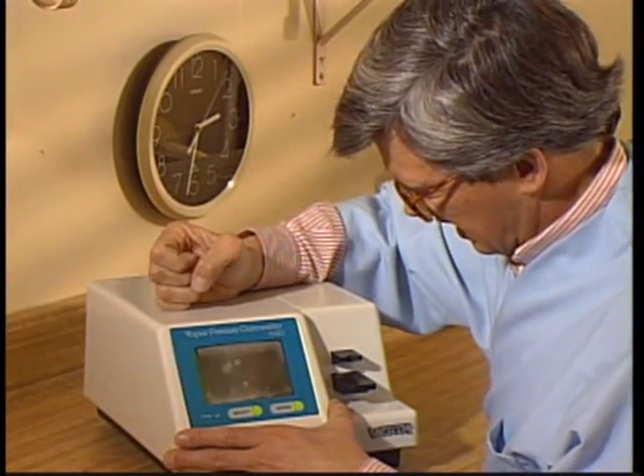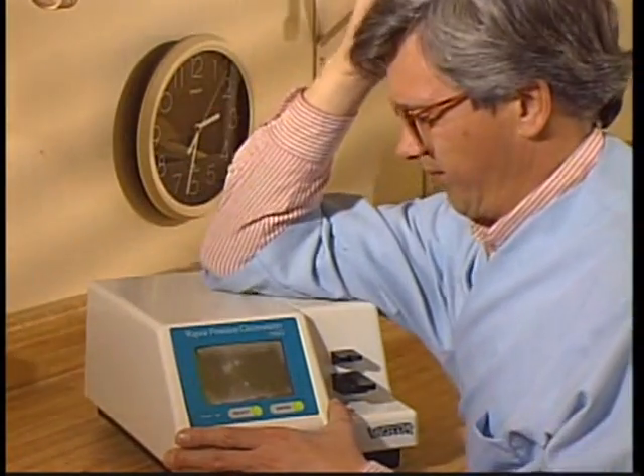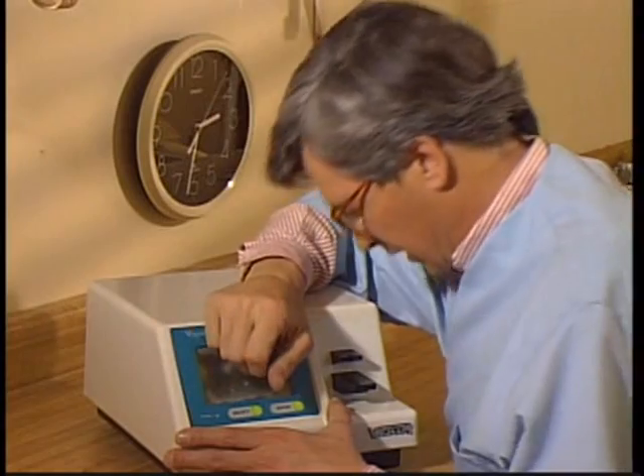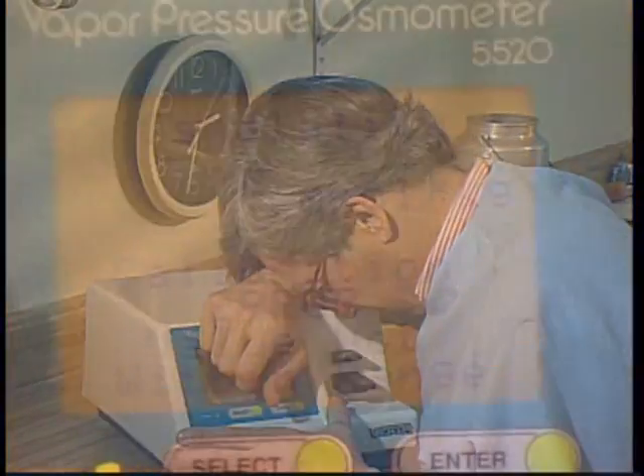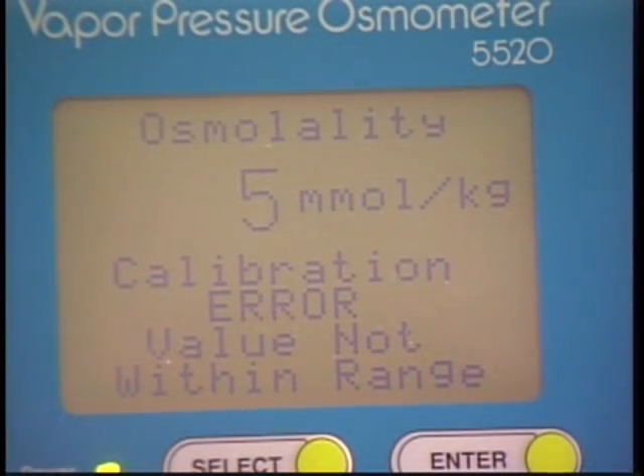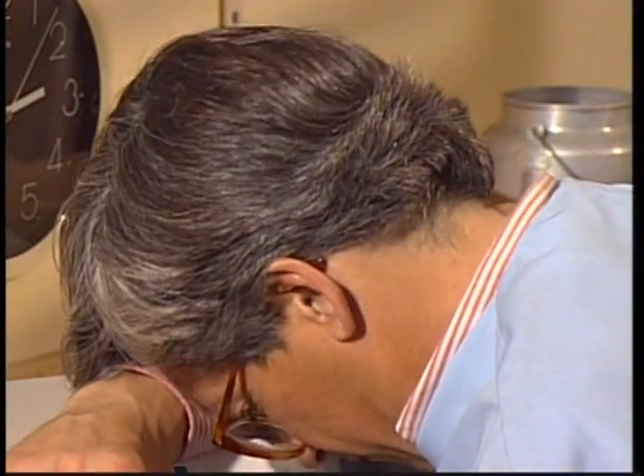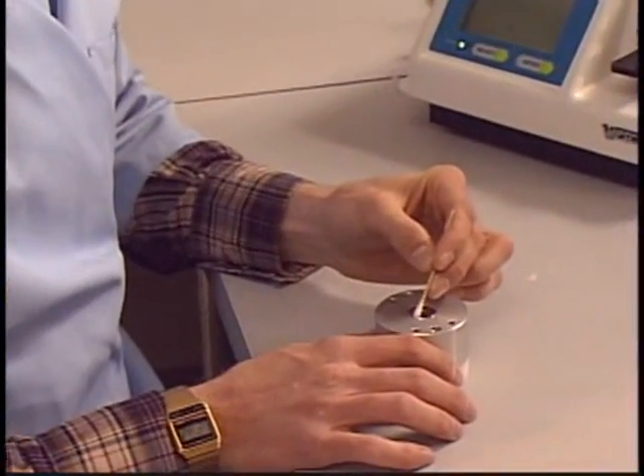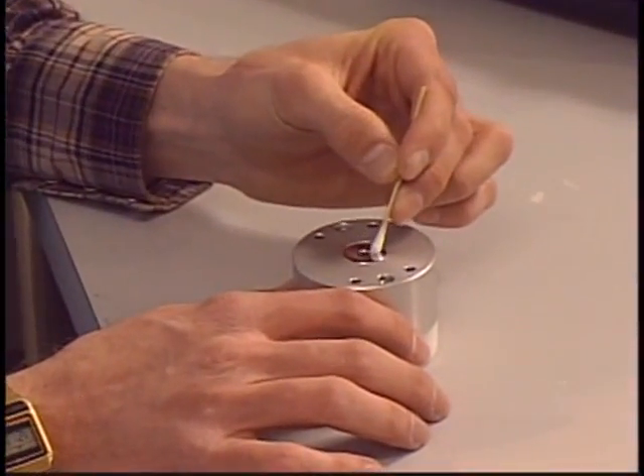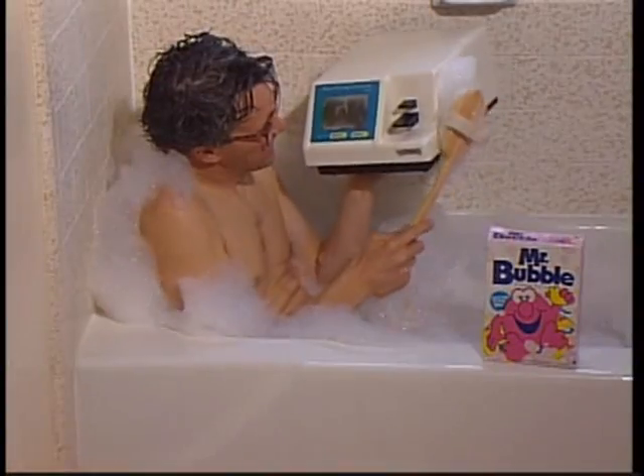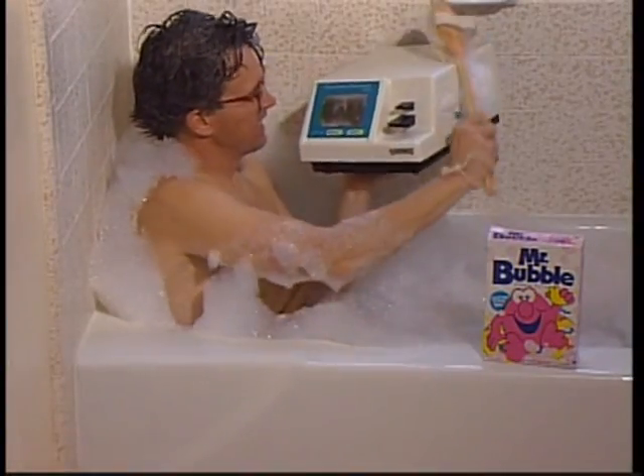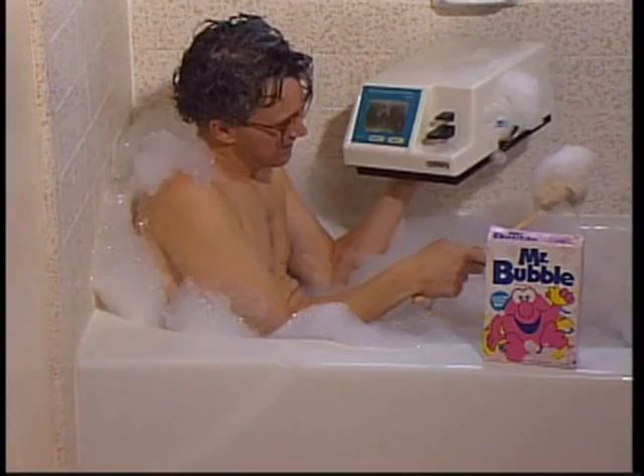If you've taken the time to play this tape, chances are your Wescor Vapro osmometer isn't working the way it should. Its LCD displays an error message or the readings seem erratic. Don't worry, the problem is probably just a dirty head. Not your head, the instrument's thermocouple head. It's a problem you can take care of with simple cleaning. Okay, so maybe not quite that simple, but it's easy, and we'll show you how.